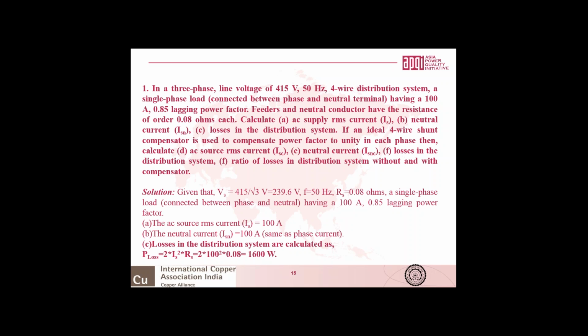Calculate the AC supply RMS current, the neutral current, and losses in the distribution system without any compensator, and if an ideal 4-wire shunt compensator is used in parallel to the load to compensate power factor to unity in each phase and to balance this load, then calculate the AC source current, neutral current, losses in the distribution system, and ratio of losses in the distribution system without and with compensator. So now coming to the solution of this interesting problem.